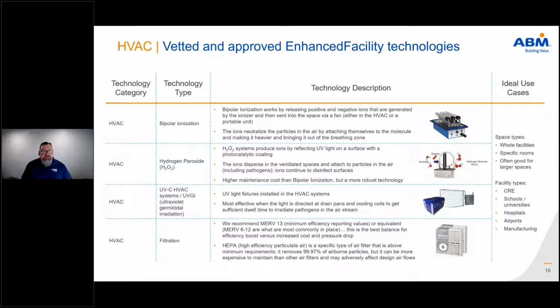As we get into hydrogen peroxide, this is another technology that's been around for a while. I think some of the original technology patents for this came out of the anthrax scare back in the 90s. This is really a UV lamp shining onto a titanium dioxide screen. The device itself is shoved up into the ductwork, so it's mixing with ambient humidity, and it makes hydroxy radicals that move downstream and attack whatever they can.